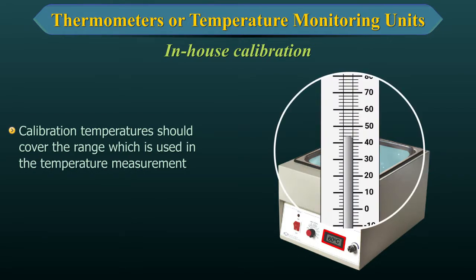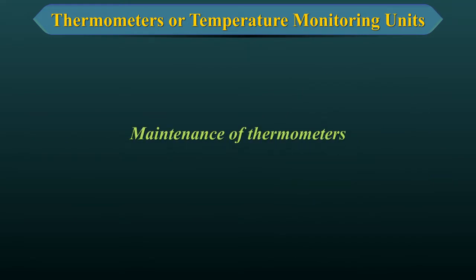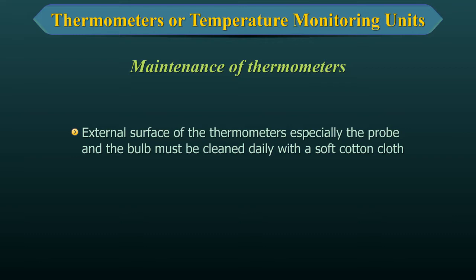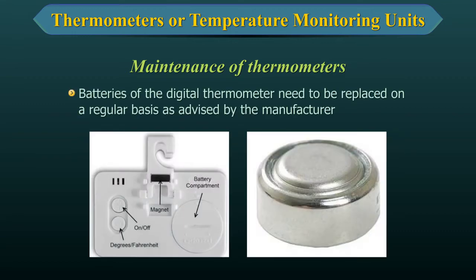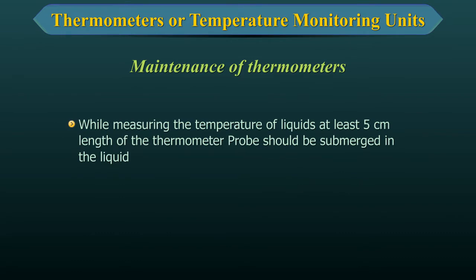Maintenance of Thermometers. The external surface of the thermometers, especially the probe and the bulb, must be cleaned daily with a soft cotton cloth. The batteries of the digital thermometer need to be replaced on a regular basis as advised by the manufacturer. While measuring the temperature of liquids, at least 5 cm length of the thermometer probe should be submerged in the liquid.